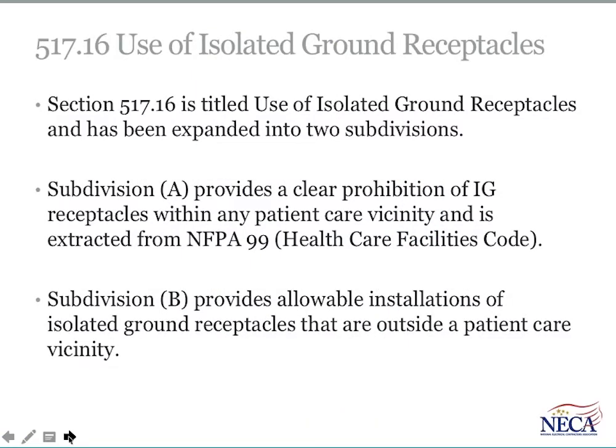I mentioned 517.16, use of isolated ground receptacles. This section was expanded, and this is related to how it appears. This rule appears in NFPA 99. What you have is a prohibition in subdivision A. So the patient care vicinity, which is a defined space, goes 6 feet from the edge of the nominal bed location, and then it goes up to a height of about 7.5 feet. Within that space, isolated ground receptacles are restricted from being installed.